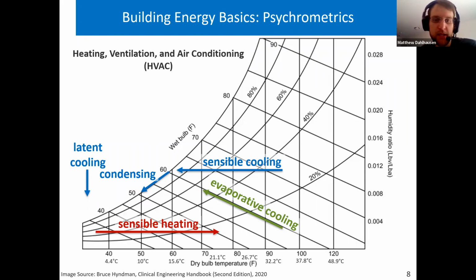The x-axis shows the air temperature, also known as the dry bulb temperature. This is the temperature reading of a typical thermometer. Moving along the x-axis is known as sensible heating or cooling. The y-axis shows the amount of water vapor in the air, also known as the absolute humidity. Moving down the y-axis is known as latent cooling.